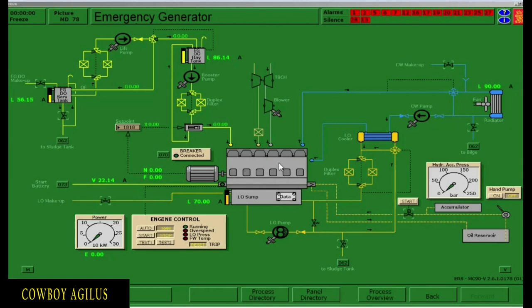The emergency generator is lined up and ready to start. All you have to do is go to the engine control, look for start, then click the button. After doing that, observe the RPM in letter N. When the RPM reaches 1,800, you can now connect the emergency generator to the emergency bus bar.